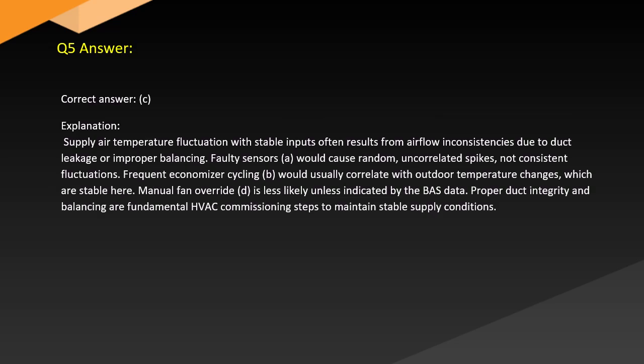Answer. Correct answer: C. Explanation. Supply air temperature fluctuation with stable inputs often results from airflow inconsistencies due to duct leakage or improper balancing.